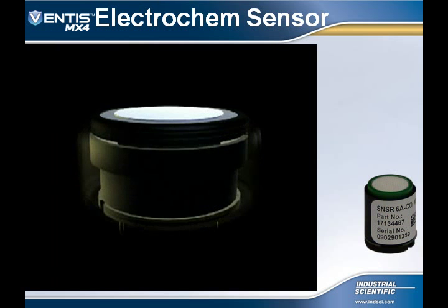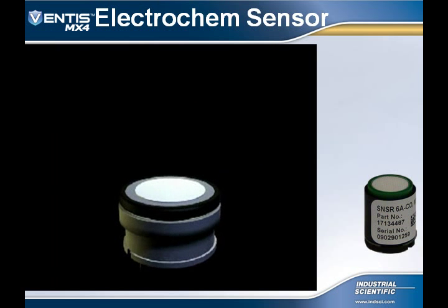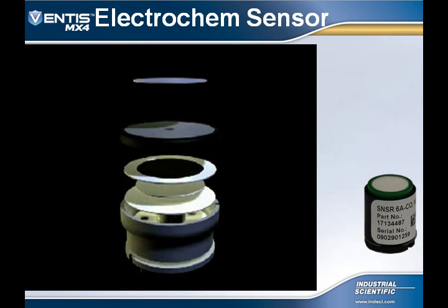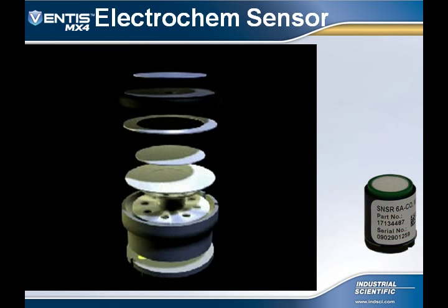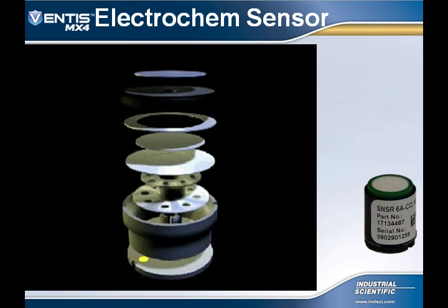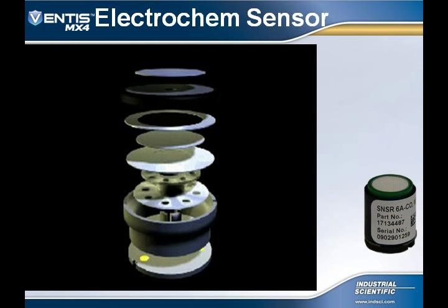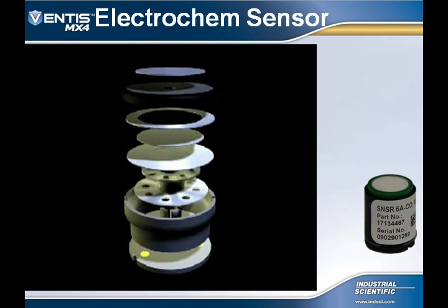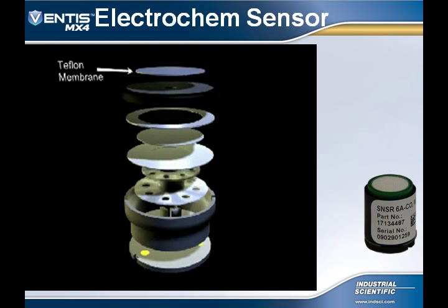The next sensor technology used in the Ventis MX4 is the electrochemical sensor. If you could see the inside of this sensor, this is what you would see. At the top is the Teflon membrane, and underneath that is the capillary tube. The capillary tube is where the gas enters into the electrochemical sensor.